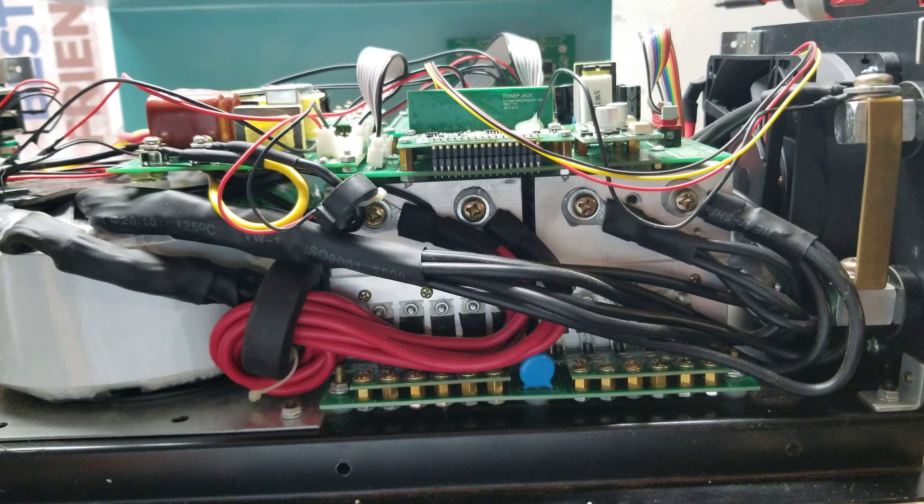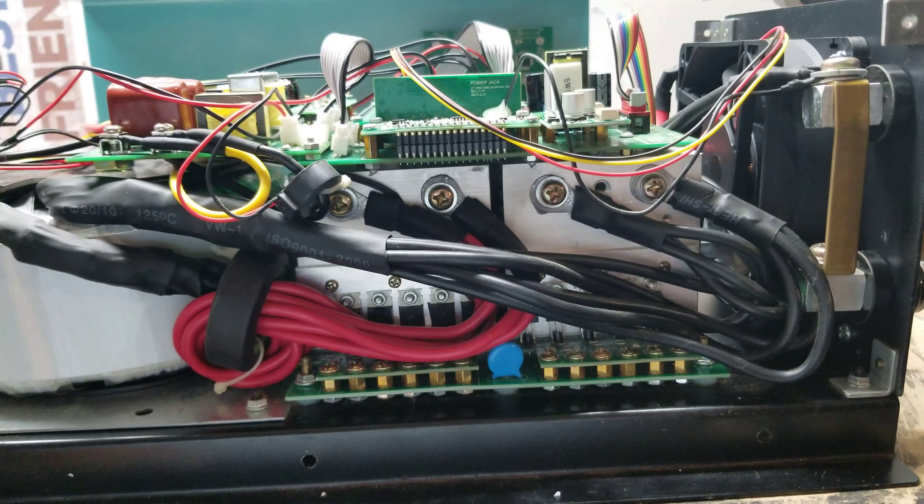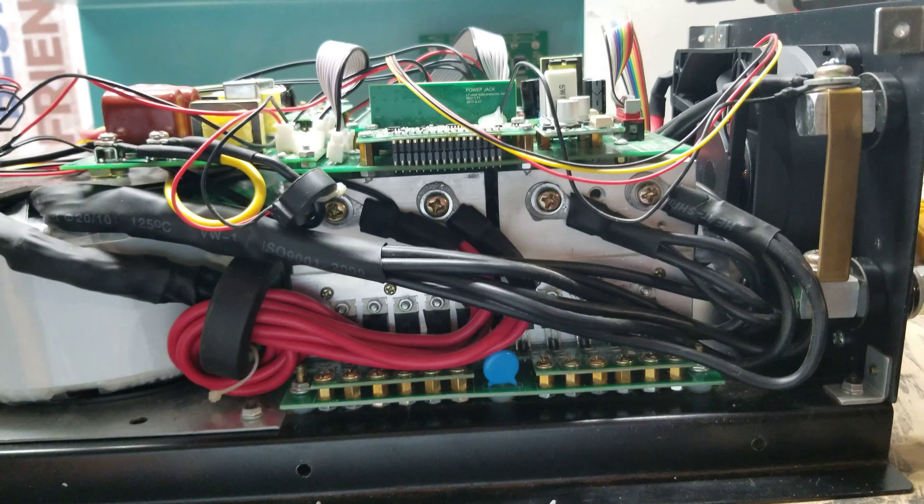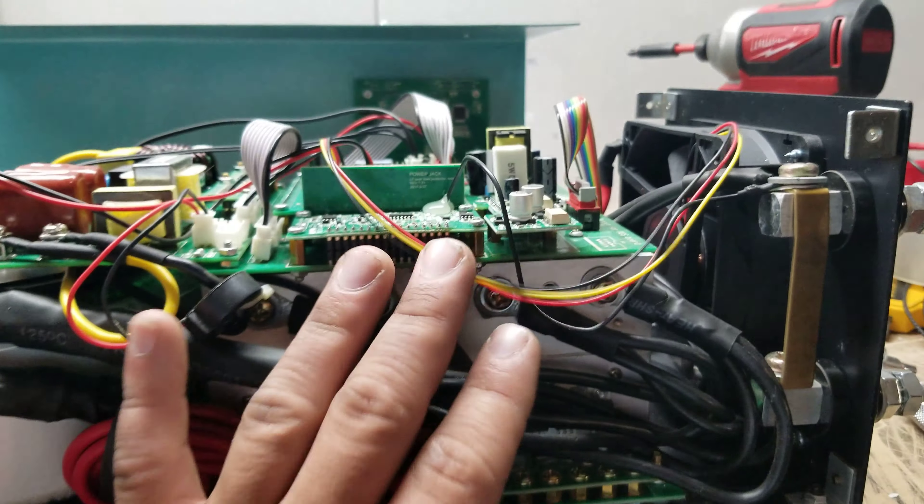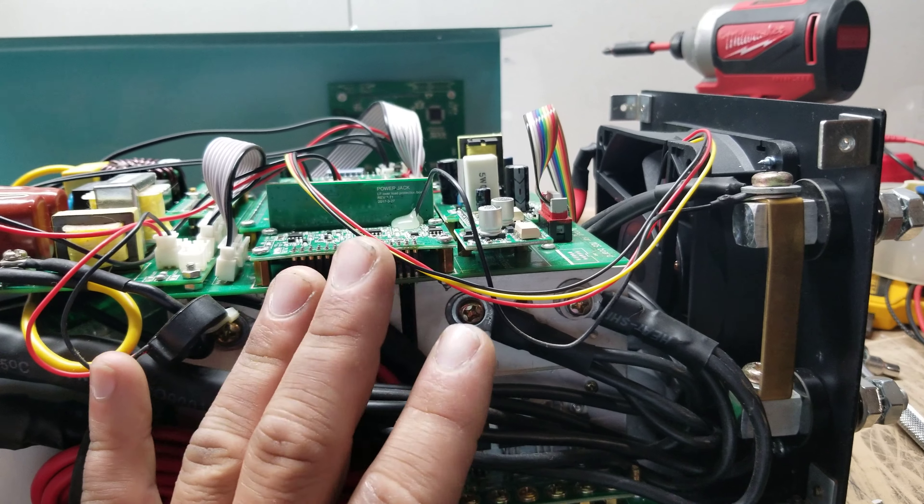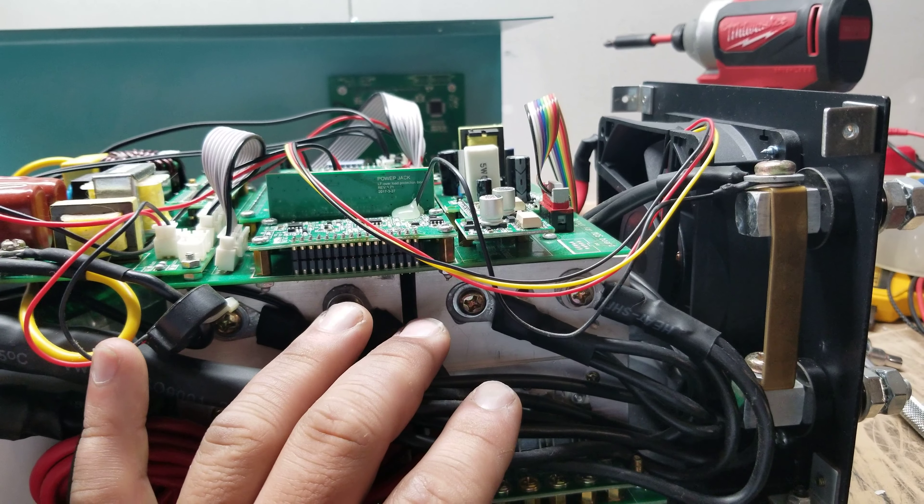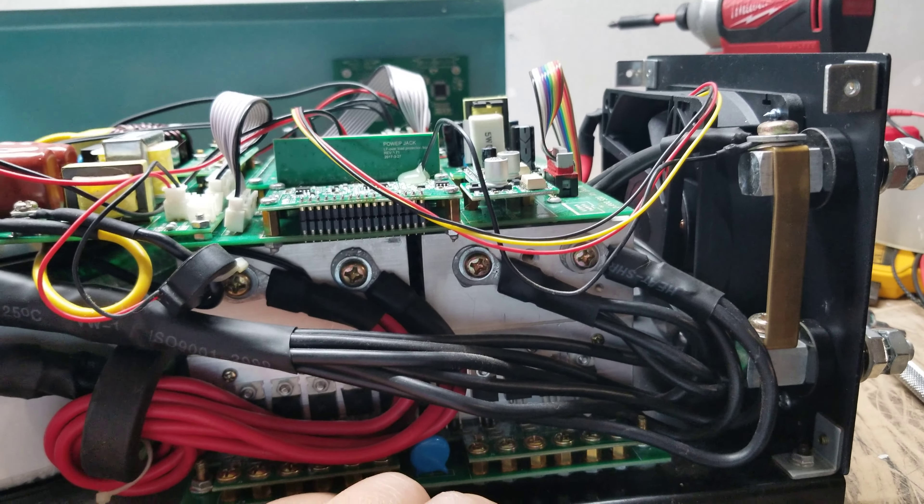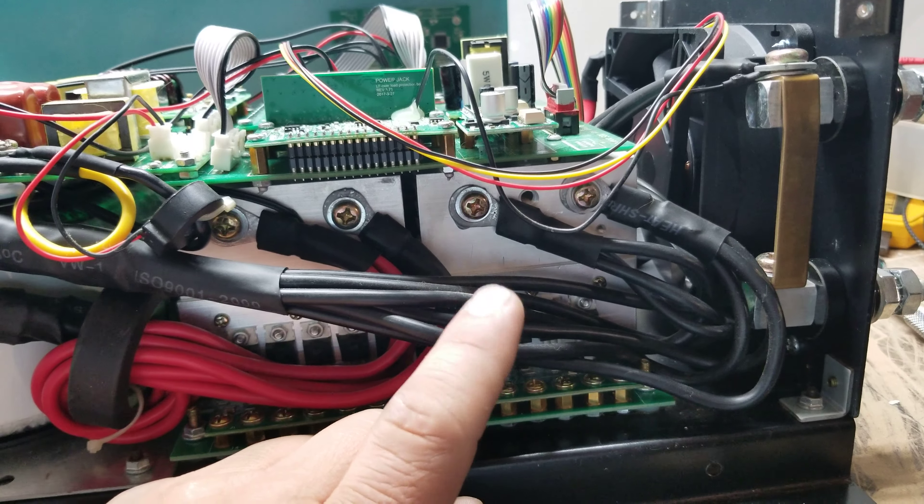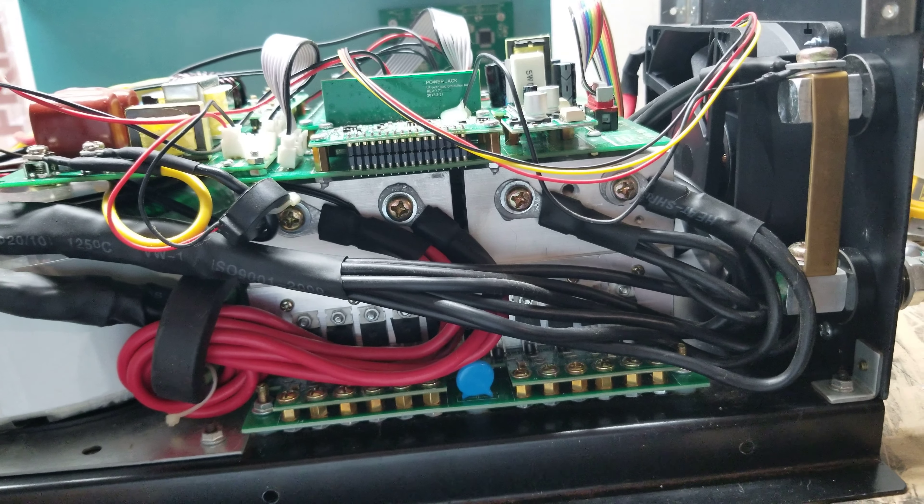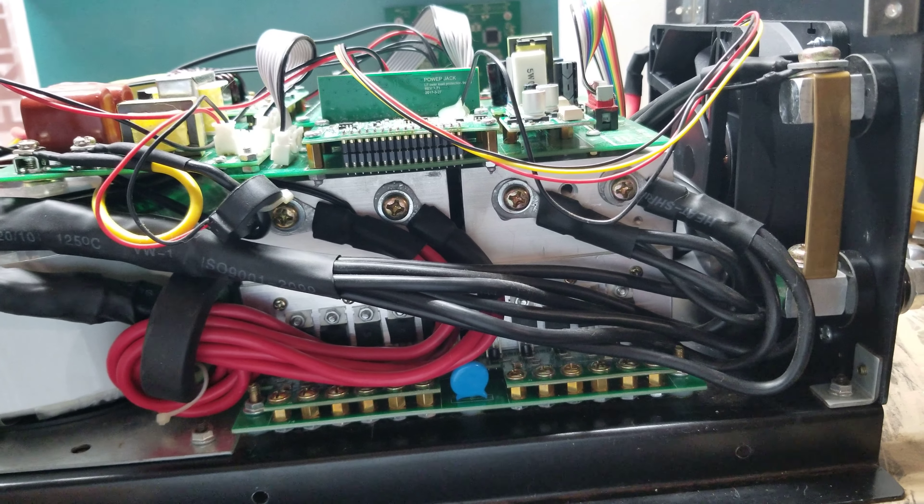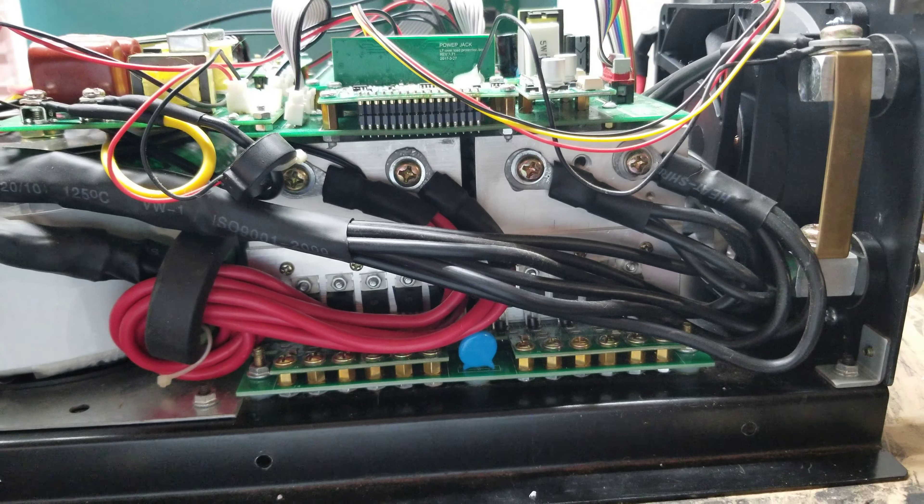Now, before you obviously power it on, just be aware that if you only replace two, as you can see, the two of the MOSFET boards were working, and then you try to power it on, it's likely that you'll damage the others or damage the new ones that you installed. So it's a good idea to just replace them all.